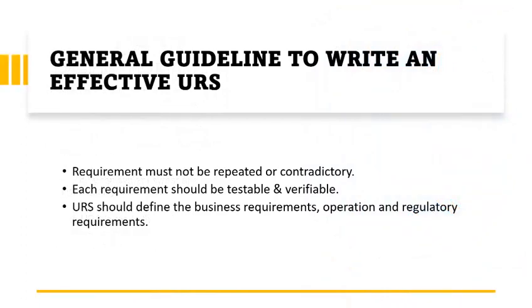In this slide we will discuss the general guidelines to write an effective URS. First, requirements must not be repeated or contradictory — each point should be clearly identified with clear instructions. Next, each requirement should be testable and verifiable, and whatever requirement is mentioned in the URS should be based on technical knowledge only.